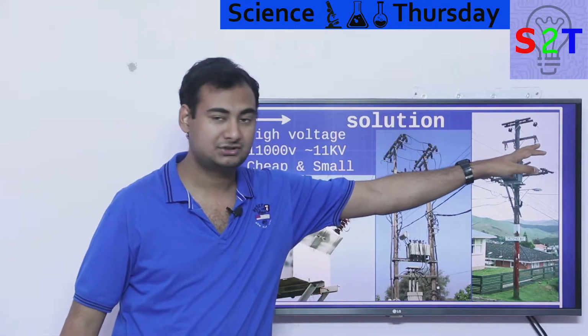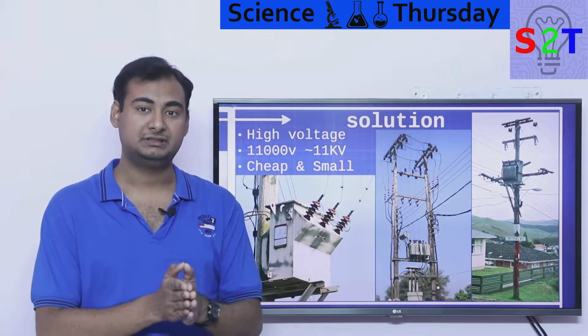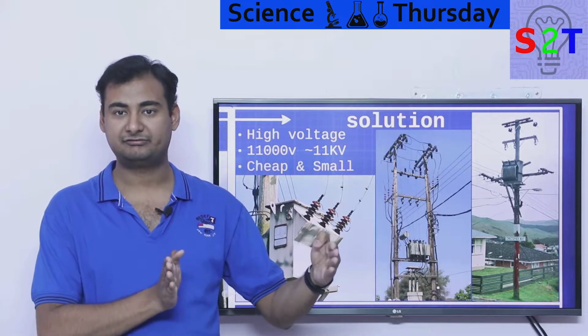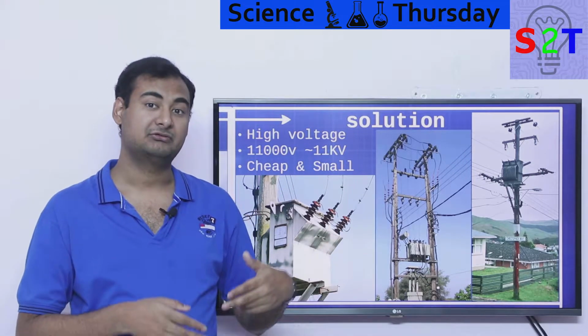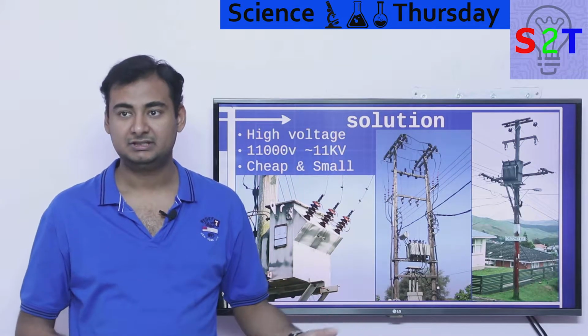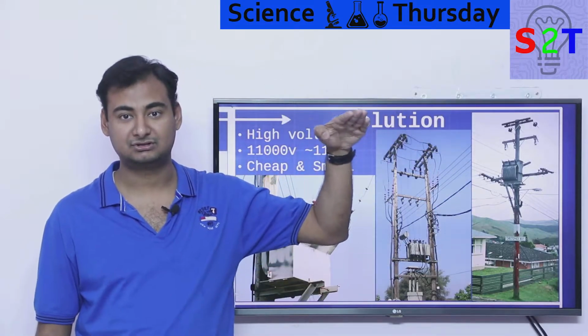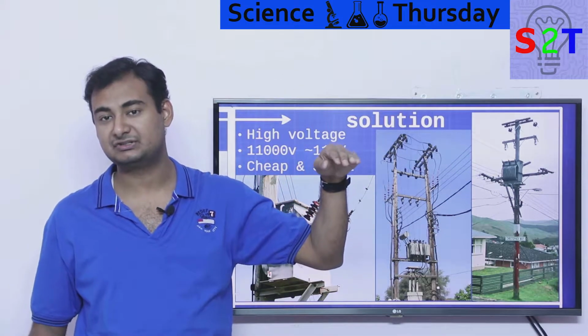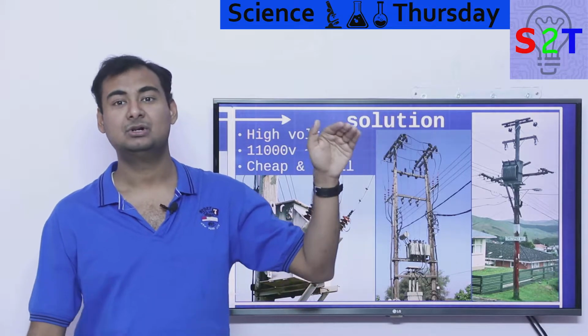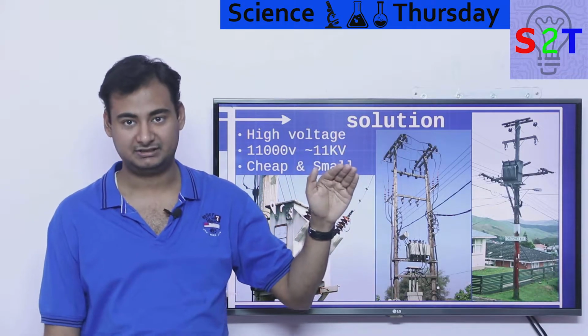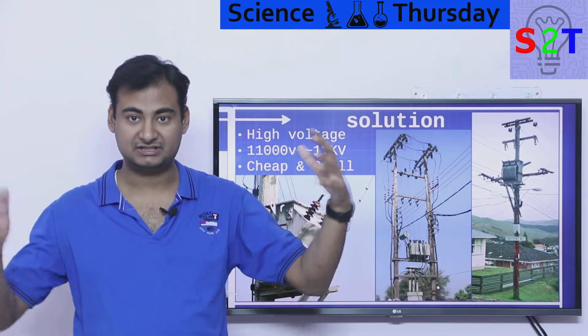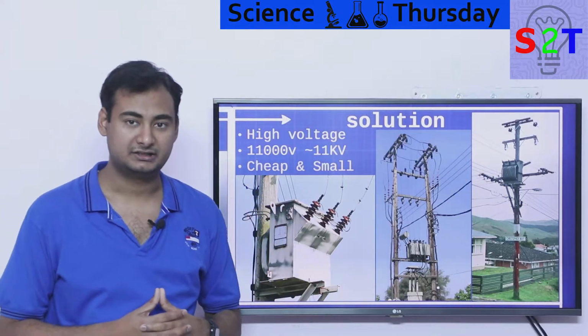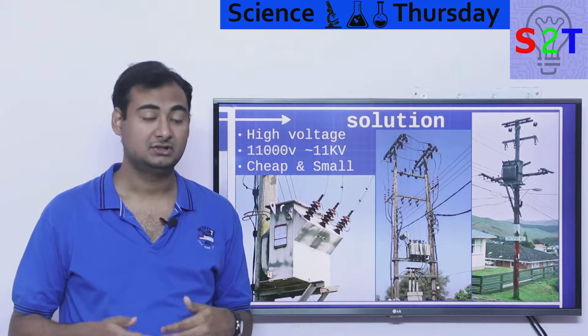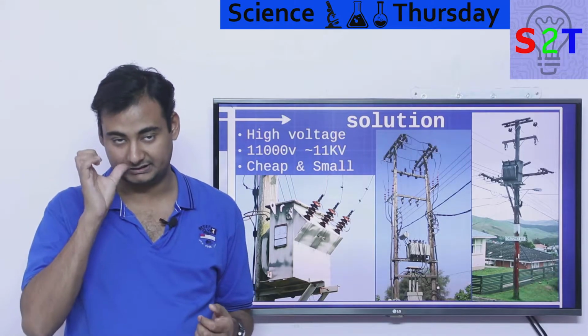So if you see the high voltage lines, they're generally separate. In 11 kV, you have to keep them, let's say, 1 foot apart. That's okay. But when you are talking about, let's say, 135 kV, you have to make sure the nearest conductors where the electricity can jump are a bare minimum of 2 to 3 meters apart, or about 10 feet apart. That's why you see giant poles carrying 100 plus kV. So that is infeasible for your neighborhood.